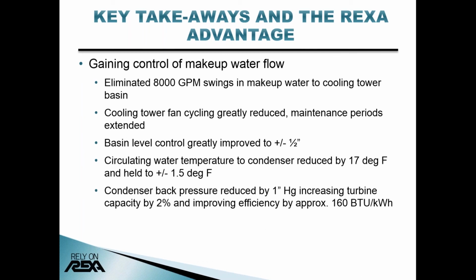And then I guess this ties into this next bullet. That's correct. As we were able to lower the circ water temperature without putting other equipment at risk, we were able to reduce back pressure. As you can see, 1 inch of mercury increase in turbine back pressure is a capacity hit of about 2%, but can improve efficiency by 160 BTUs per kilowatt hour.